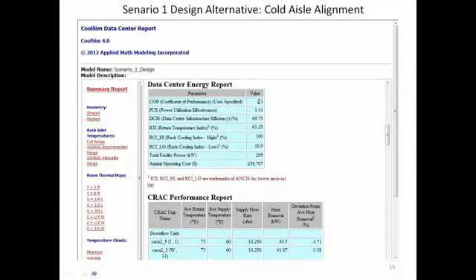However, the only thing you run into when you do cold aisle like this is the room gets kind of warm, and here's a slice at 6 feet of what's going on in that room under these conditions. You got 60-degree air in the center where the cold aisle is, but the rest of the room is 81, 80. Well, it's high 70s up to 80, 82 almost of temperature. So probably lowest cost option from the point of view for them of not putting a ceiling plenum in place or anything, but again, not optimal either, right, Matt?